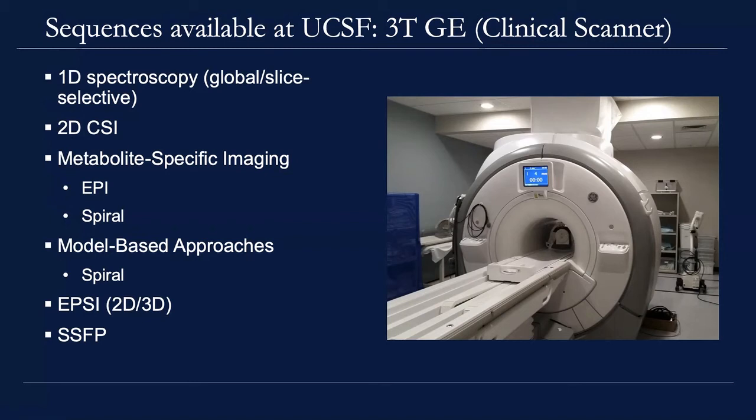Your B1's higher, but your gamma's lower, so it all washes out. For spectral spatial, it's almost never an issue because your pulses are so long. You could consider a scenario where, if you were doing really advanced or short TR SSFP at high tip angles, SAR could be an issue. Or going to 7T versus 3T, SAR could be an issue. But for the spectral spatial type experiments, it's never really a problem. But good question.